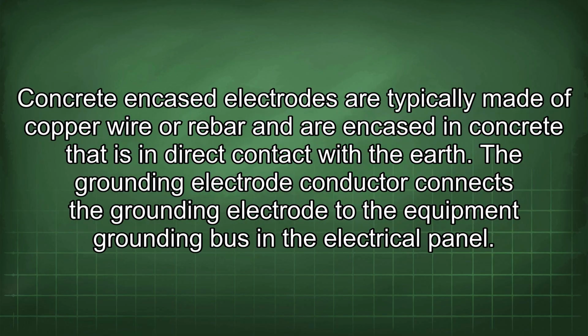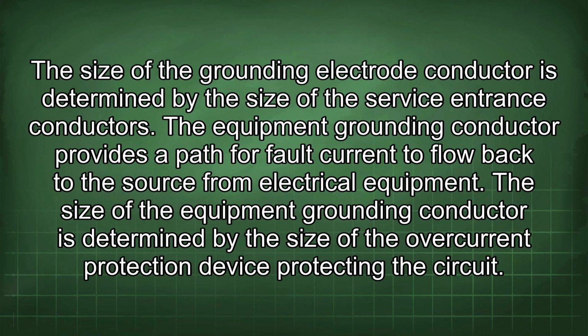Concrete encased electrodes are typically made of copper wire or rebar and are encased in concrete that is in direct contact with the earth. The grounding electrode conductor connects the grounding electrode to the equipment grounding bus in the electrical panel. The size of the grounding electrode conductor is determined by the size of the service entrance conductors. The equipment grounding conductor provides a path for fault current to flow back to the source from electrical equipment. The size of the equipment grounding conductor is determined by the size of the overcurrent protection device protecting the circuit.